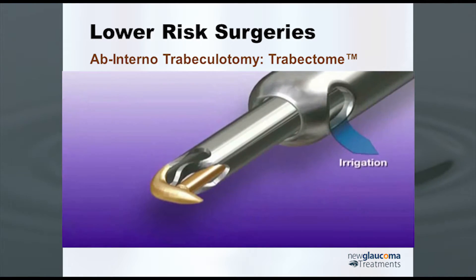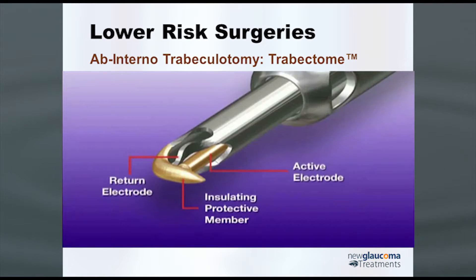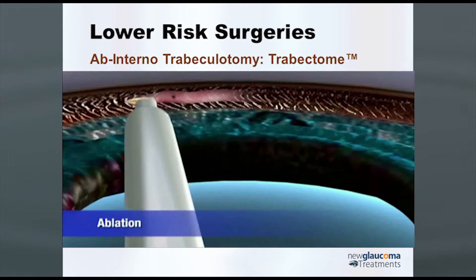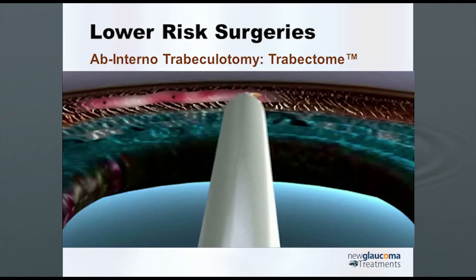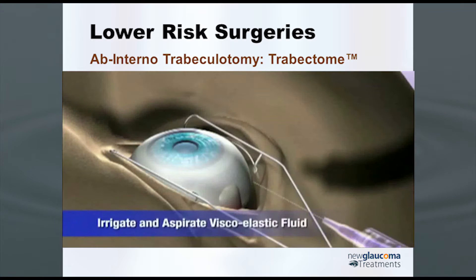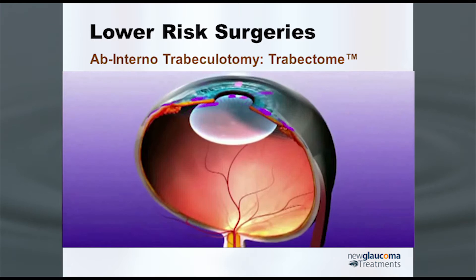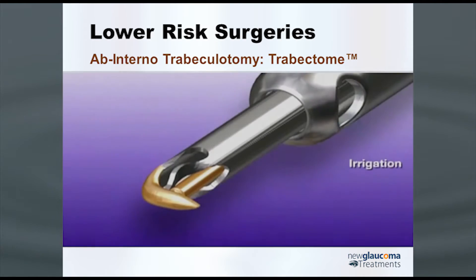This is the instrument here, and it's a pretty cool looking instrument. It has a foot plate to protect the posterior wall of the canal, and essentially it's got these electrodes that produce a plasma, and then it sucks up the trabecular meshwork tissue as it opens up the canal. It's about a $50,000 instrument, and then they make you purchase each of the hand pieces.